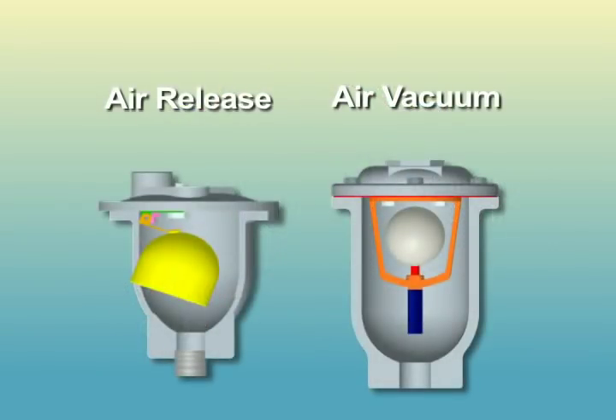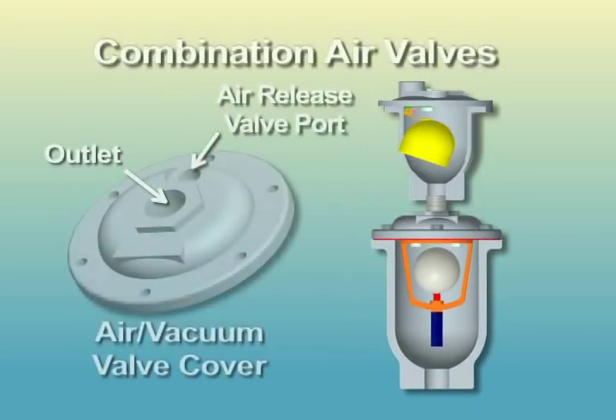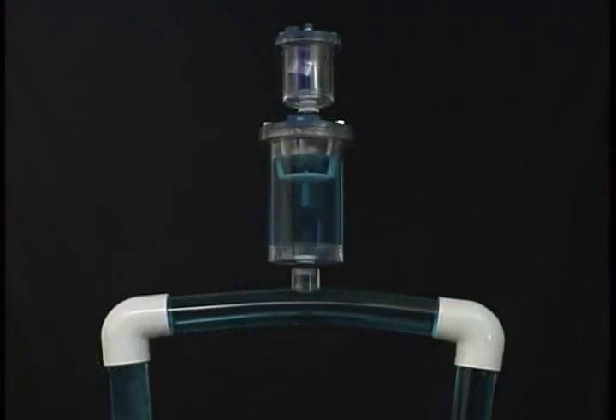Air release and air vacuum valves each perform specific functions. Combination air valves are designed to perform both. Combination air valves are the most commonly used of air release valves. They perform the functions of an air vacuum valve and air release valve. Shown here are an air vacuum valve and air release valve piped together to form a combination air valve. Notice that the air vacuum valve stays closed while the air release valve continues to function during system operation.